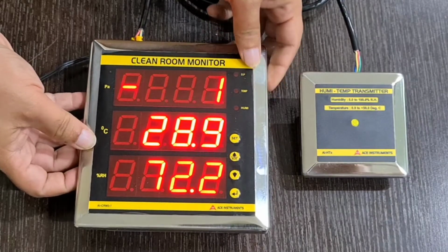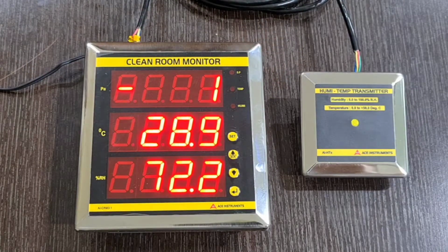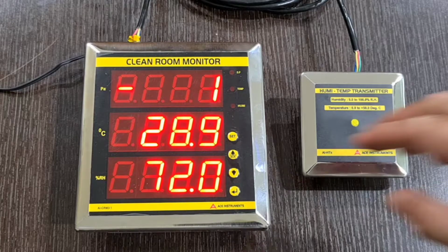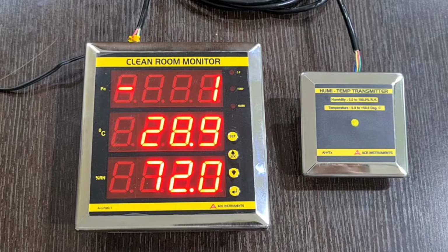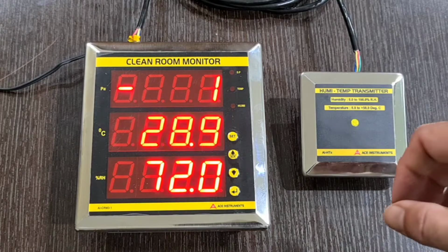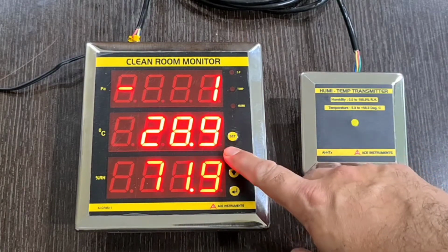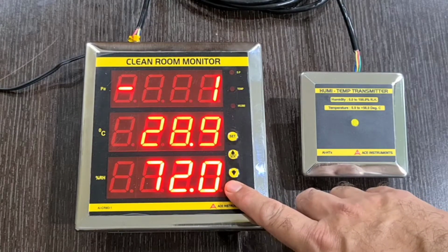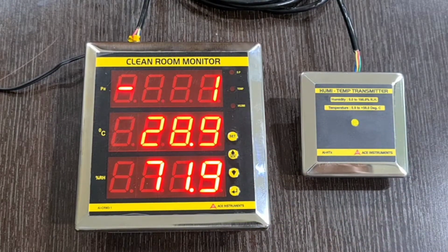The ACE Clean Room Monitor finds extensive applications in hospital operation theatres, pharmacies, and AHU monitoring units. The instrument comes with a powder coated stainless steel back box with a stainless steel front flush plate. The menu programming, the buzzer alarm setting, and also the Modbus communication settings are field programmable using the tactile keypad on the front panel of the instrument. The menu programming is multi-password protected, thus avoiding unauthorized access to the inner working.